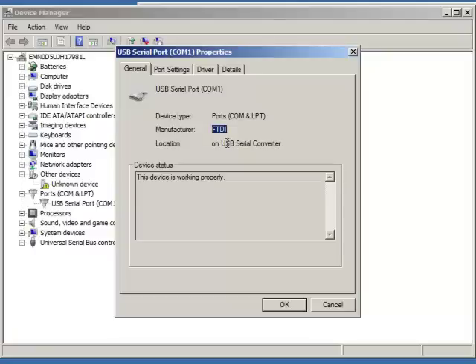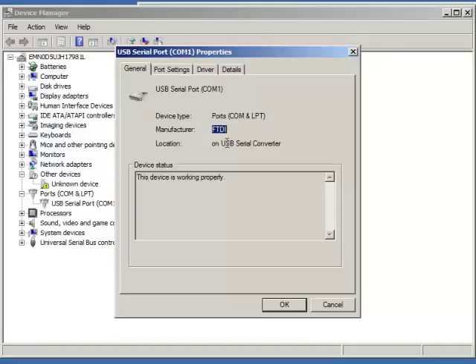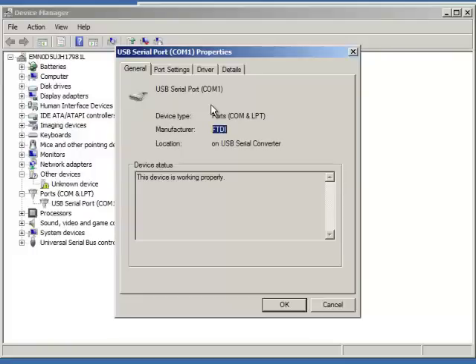The Prolific chipset will work on XP. It does not work on Windows 7. There are several other device manufacturers with different chipsets. We have not gone through and cannot go through the entire marketplace and test all the different manufacturers. You can try going to their website and updating the device drivers. If you're not able to establish communications, the best choice would be to purchase the USB 2920 with the FTDI chipset.